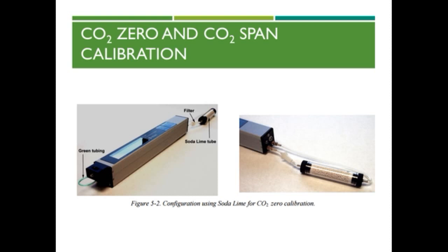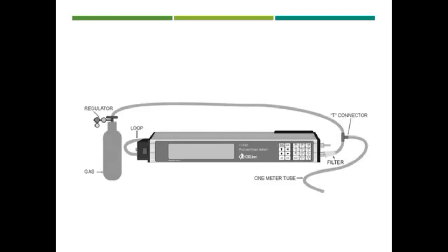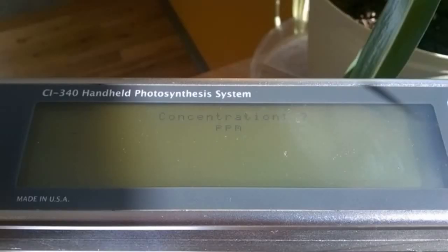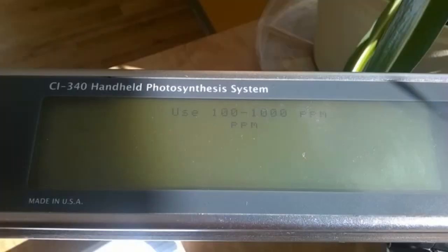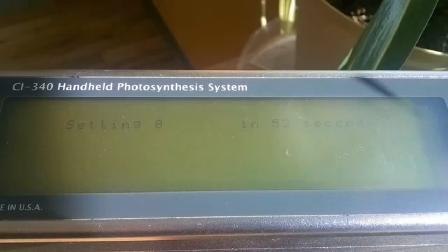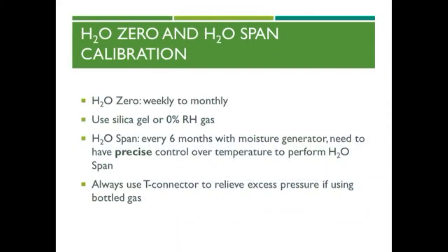If the sensor is due for its 6-month CO2 span calibration, connect a known concentration CO2 gas standard following the instructions provided by this diagram. Press Start. The unit will display concentration in ppm. Enter the known CO2 concentration ranging from 100 to 1000 ppm. Hit Start. The instrument will count down from 60 seconds and set the CO2 span. Press Start one final time to save the calibration. The display will return to the original Calibrate CO2 screen when you're finished.